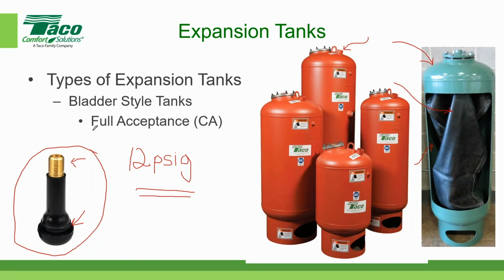The reason we call it a full acceptance tank is because the physical volume of the bladder is the same as the physical volume of the steel container. So in our example here, if the steel container happened to be 200 gallons, that steel container, I'll just put a G in here, is equal to the bladder volume. So the steel container and the bladder are the same. Hopefully I spelled that correctly, Brett. Spelling has never been one of my best attributes. So a full acceptance tank has a bladder whose volume is equal to the steel container volume.